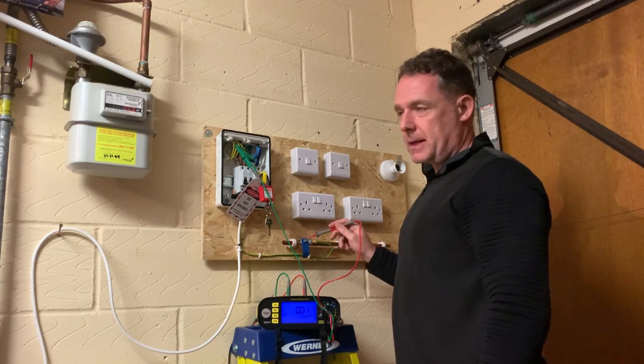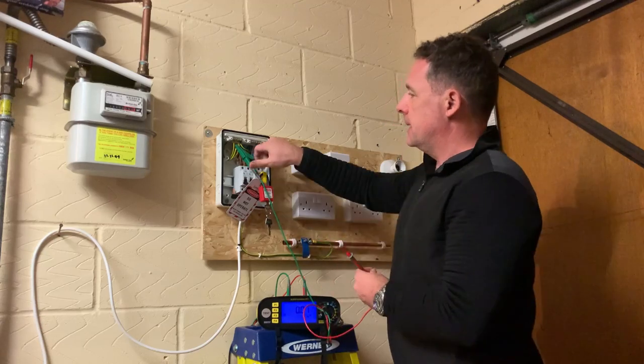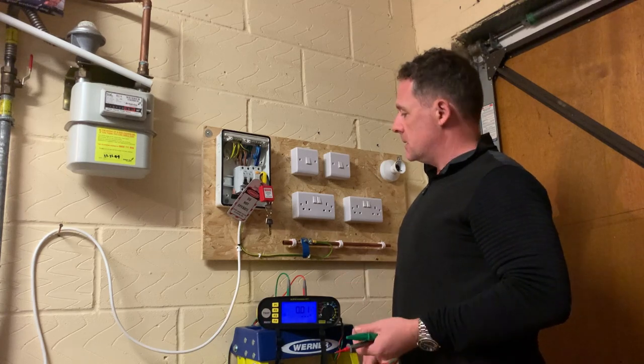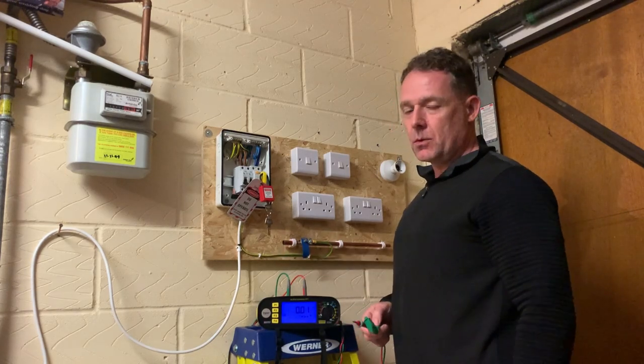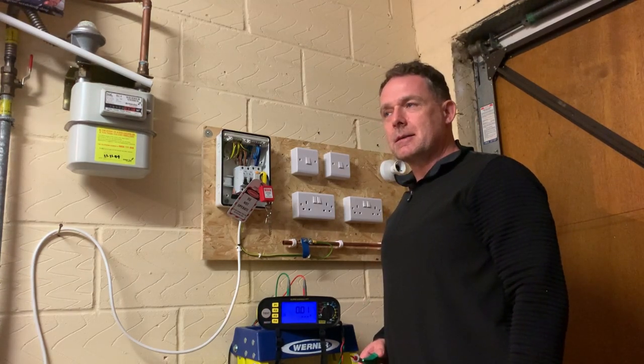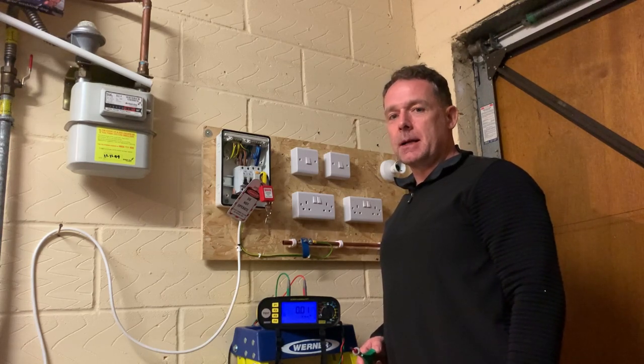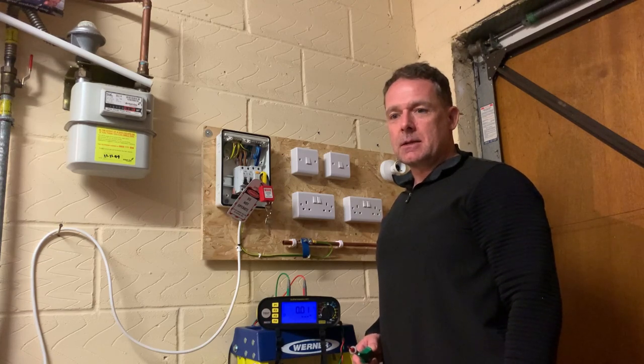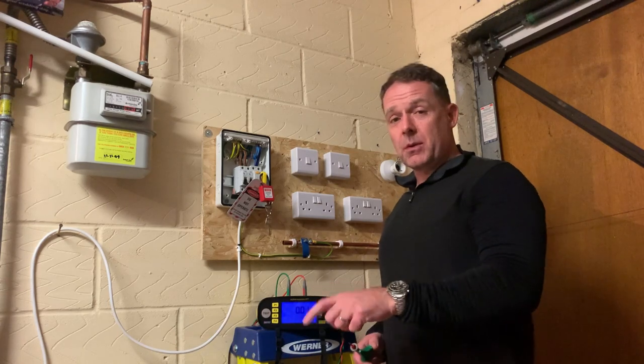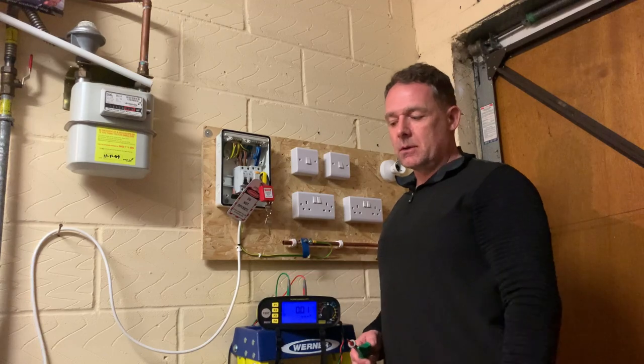So that's fine, and you'd expect that as well - this is such a short run. In a house you'd be expecting 0.05 ohms or less as a good reading. That's based on a 10mm squared bonding conductor and no more than 27 metres. If you look in the on-site guide table 4.4, you'll see it gives a listing of CPC sizes in relationship to the main live conductor sizes - I'll put a snapshot of it in the video.